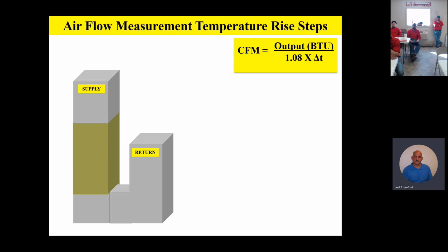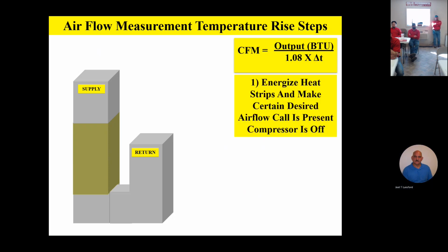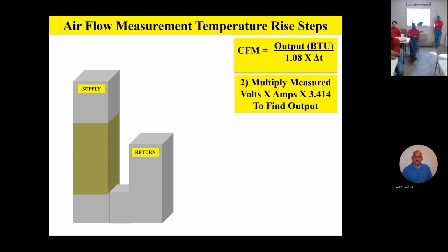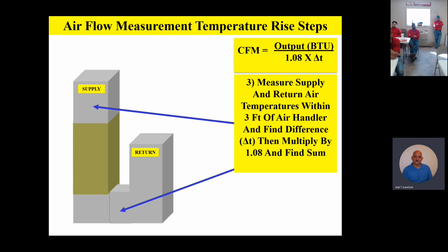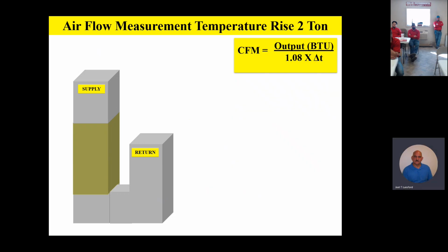Guys, one other thing I wanted to throw at you quick in this airflow measurement is kind of an old method of doing airflow. It involves a little bit of math, and we'll breeze through this. But basically, if you've got a voltmeter and an amp probe, you can energize your heat strips like on an air handler, and select the speed tap that you're wanting to check. You can then multiply your measured volts times your amps times a mathematical constant of 3.414. That gives you the output portion of the formula.